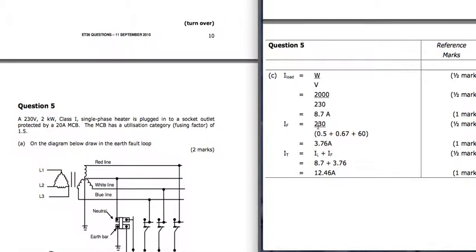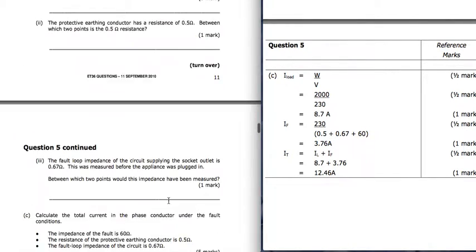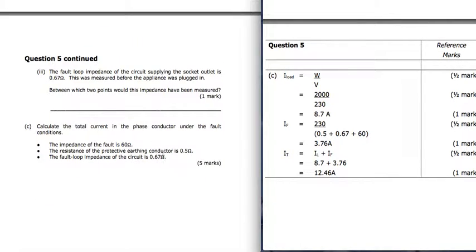But we've also got a fault, and that fault is made up of the 0.5, which is the protective earth conductor, the 0.67, which was the earth fault loop impedance, and the 60 ohms, which is the impedance of the fault. So that's quite a high resistance there. Gives me 3.76 amps. If we add those two together, you get just over 12 amps.